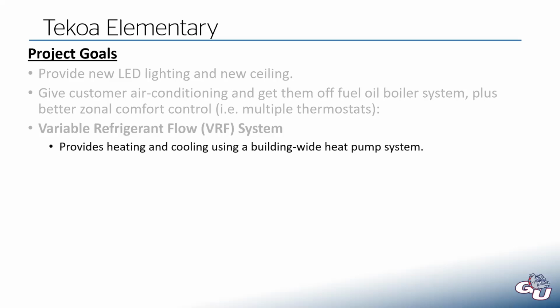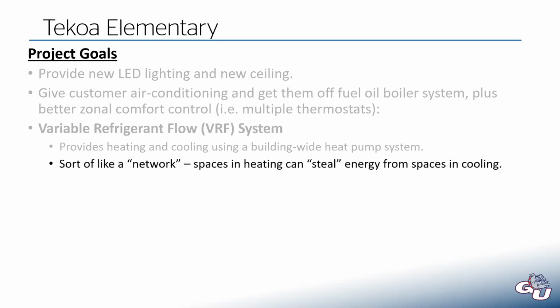What a VRF system can do, it can provide both heating and cooling using a building-wide heat pump system. So recall that a heat pump can provide heating and cooling using refrigerant. And it's using the same components, it's just reversing the process, whether it's in heating mode or cooling mode. What makes a VRF system very efficient is it acts as kind of a network. And what this means is that if you have some spaces that are in heating mode, meaning they want heat energy because they're getting cold, they can take that heat energy from other spaces that are trying to get rid of heat because they're in cooling mode. I'll talk a little more about that here in a minute.